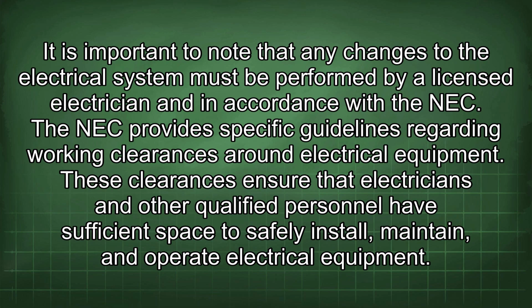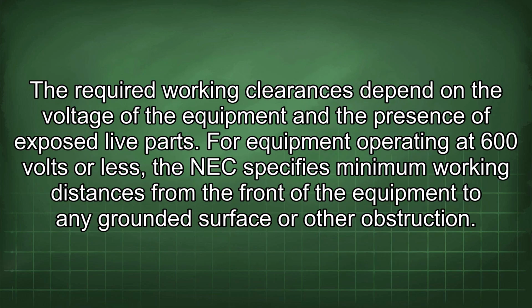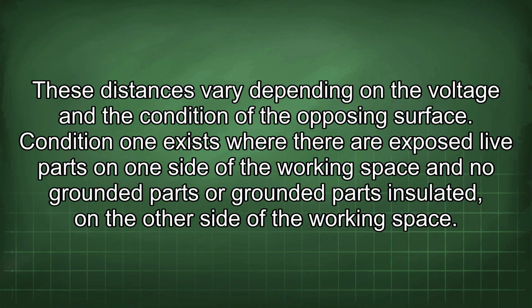The NEC provides specific guidelines regarding working clearances around electrical equipment. These clearances ensure that electricians and other qualified personnel have sufficient space to safely install, maintain, and operate electrical equipment. The required working clearances depend on the voltage of the equipment and the presence of exposed live parts. For equipment operating at 600 volts or less, the NEC specifies minimum working distances from the front of the equipment to any grounded surface or other obstruction. These distances vary depending on the voltage and the condition of the opposing surface.